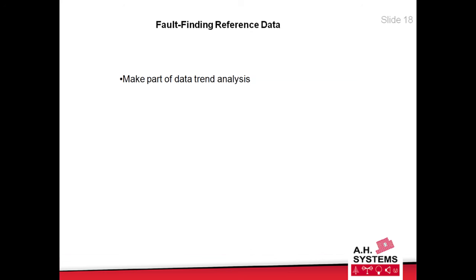But another reason for doing that anyway is auditors love data trend analysis. They love it if you, as a test manager, are keeping an eye on the performance and looking for degradation of your test system. So if you have information filed away in your filing cabinet and the auditor asks about such matters, you can pull it out and say, every 3 months we make this test, and as you can see over the last 3 years there has been no degradation in performance. They love you. It puts you in very good stead during the audit.